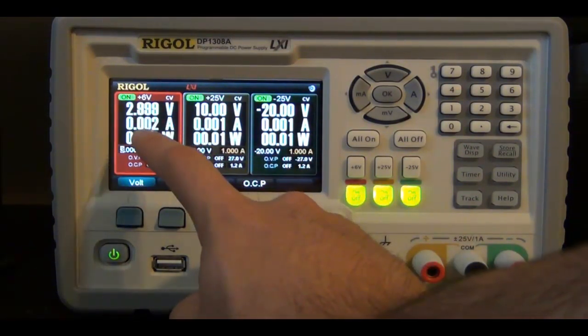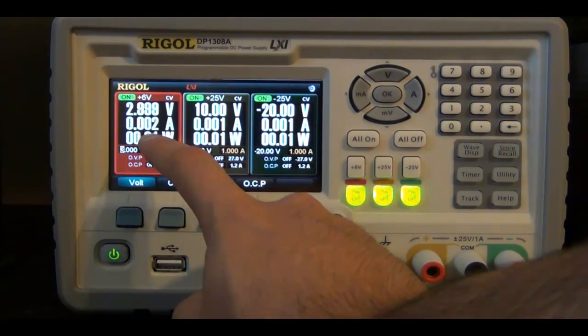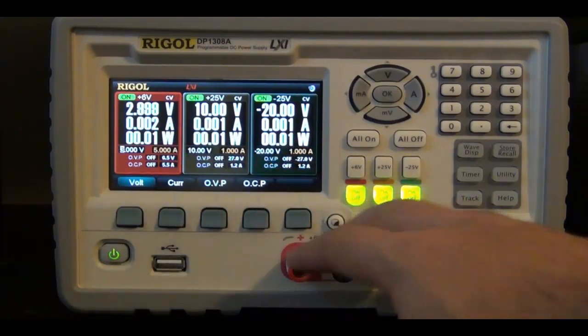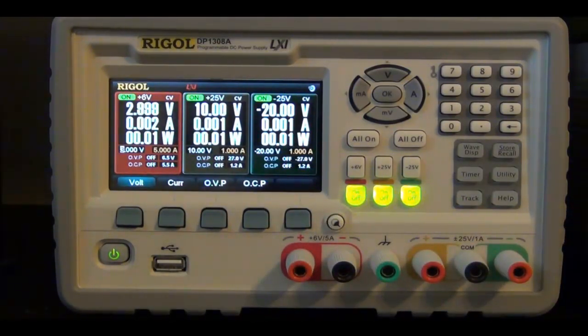There is some offset current being displayed, even though nothing is connected. That's still within the spec of the power supply, but can be calibrated out if you need to. Right now the power supplies haven't warmed up yet. I just turned them on, so there will be some offset, and once they warm up, that should go away. And even if it doesn't, there's a way to calibrate them out, and I'll show you in just a second.